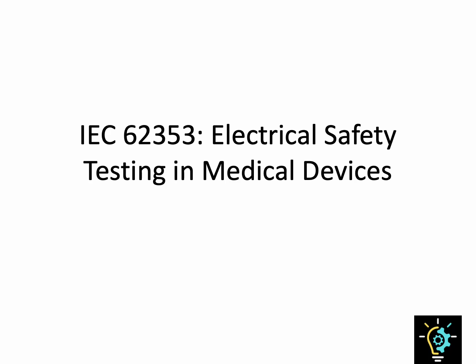Welcome to this session on IEC 62353. This is the international standard that governs recurrent and post-repair electrical safety testing of medical electrical equipment. Think of this standard as the counterpart to IEC 60601. Whereas IEC 60601 focuses on type testing before a device actually goes into the market, IEC 62353 deals with what happens afterwards, in hospitals, clinics, and repair shops where devices are used and maintained daily.